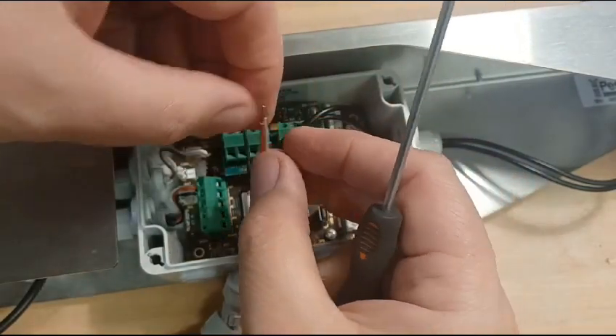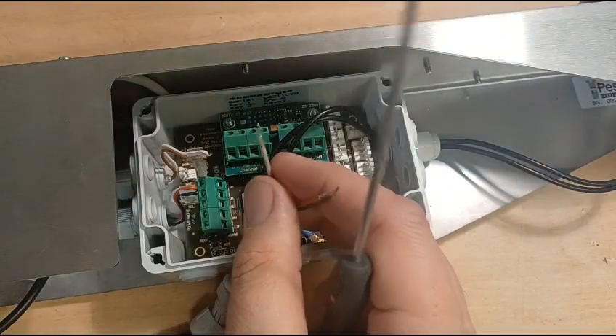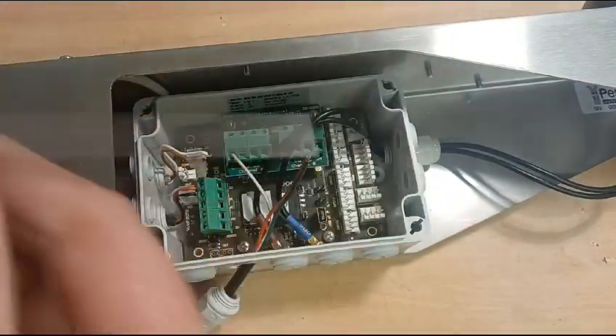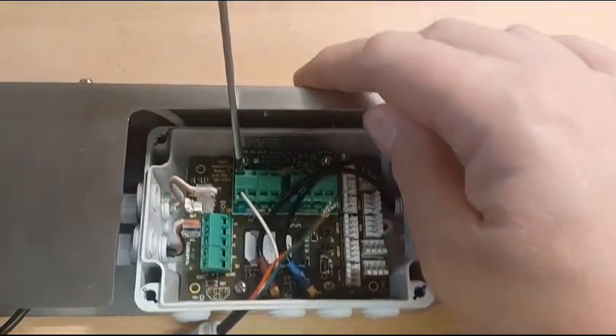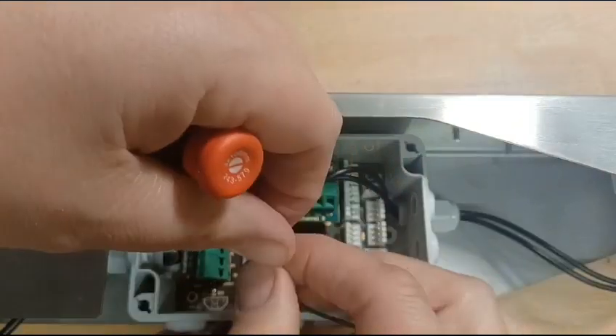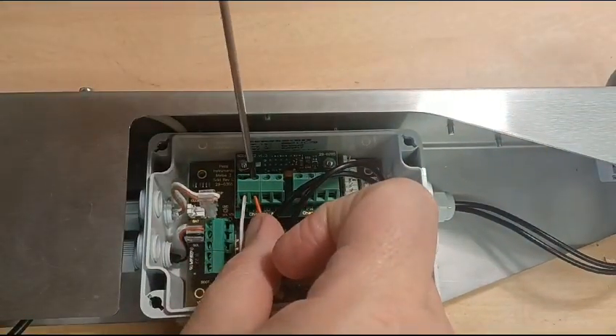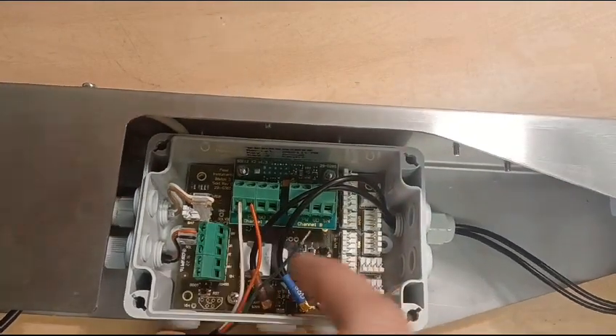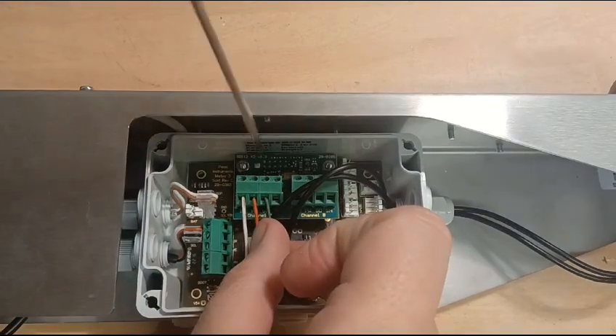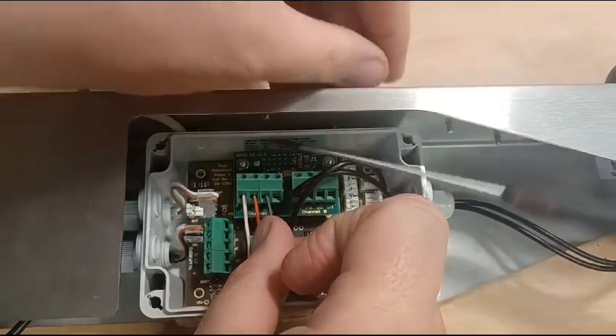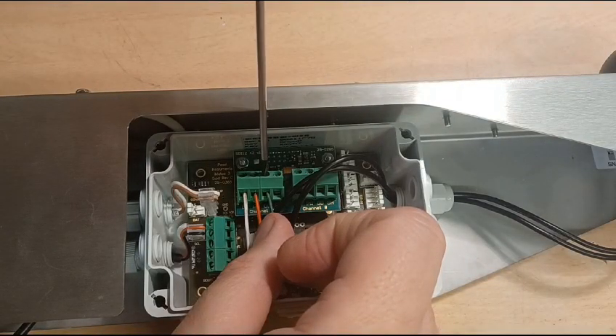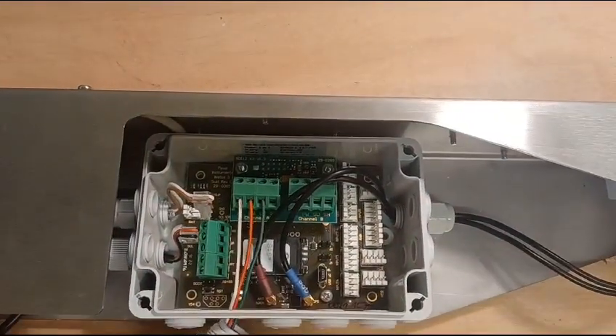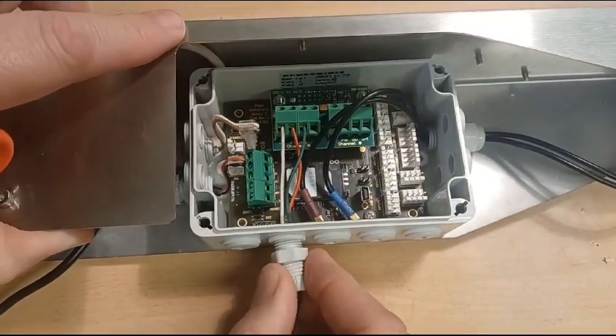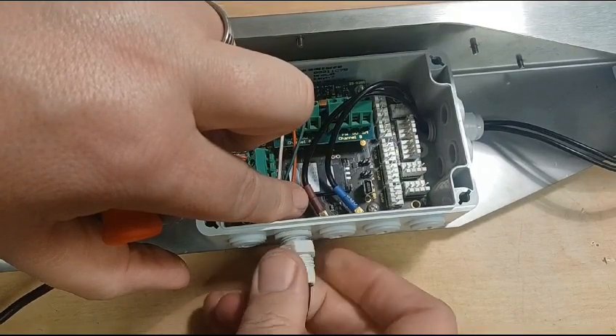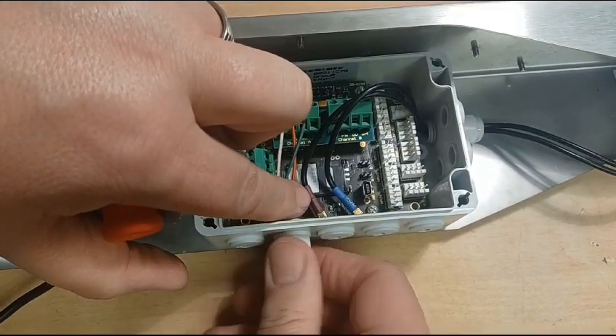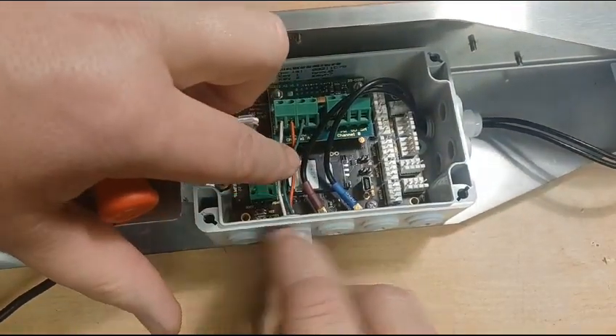And then, so you're going into extended A, so it's white, and then power, red. Underneath the block it says where you're supposed to put them, and then green is ground. Then put the grommet or the gland into the socket, just gently twist it in. You don't need to tighten these really tight, just finger tight, the plastic washer kind of tightens it anyway.